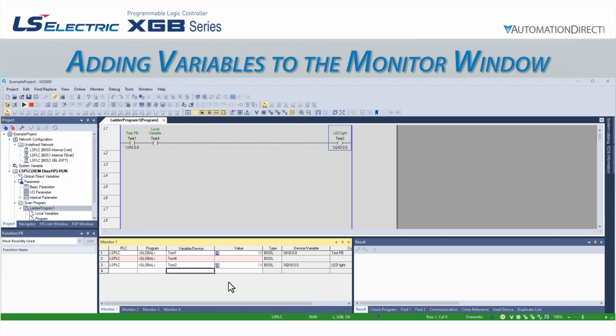It is important to know if your variables are global or local variables. As we add test4, it defaults to a global variable, but since test4 is a local variable, it shows no status since a test4 global variable does not exist. We need to change the program heading to Ladder Program 1 to get the status to appear. This can get very confusing if you use the same variable name for a local and a global variable. It is recommended to name your variables unique names to avoid this confusion.